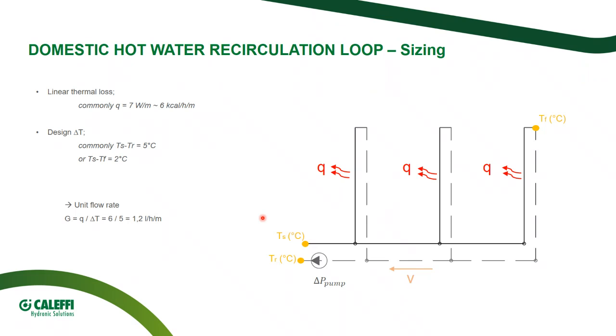There are two ways commonly. The most common is to state between supply and return a delta T of 5 Celsius degrees. This is one of the most popular ways of designing. The other one states that between supply and the farthest point of the system, I shall keep 2 Celsius degrees. The final result is almost equivalent. So if I combine these two values, I obtain a unit flow rate per meter of pipe of 1.2 liters per hour. So for every meter of pipe of my system, I have to supply at least 1.2 liters per hour. So it depends on the length, basically.